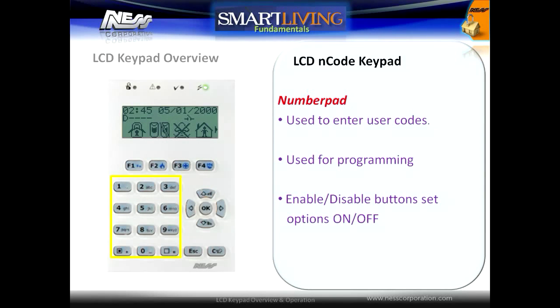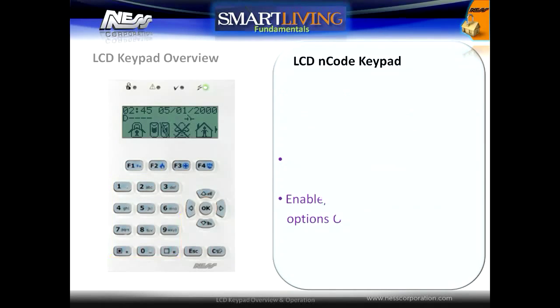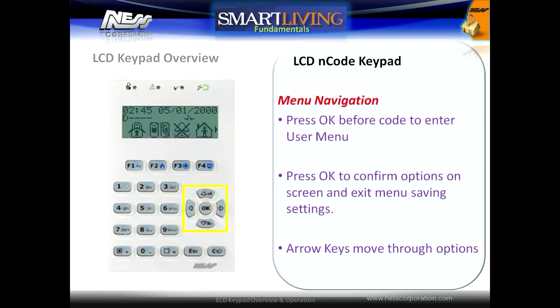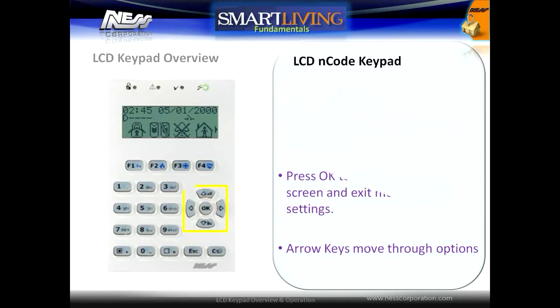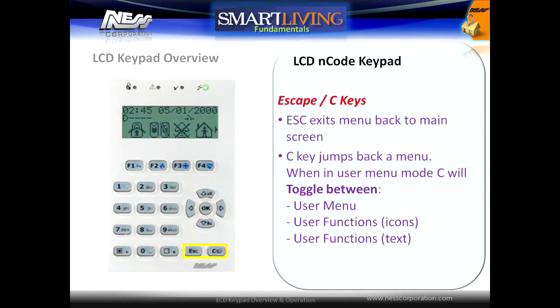The number pad is used for user code entry, for programming, and the enable/disable buttons at the bottom are used to switch options on and off. The menu navigation keys allow the user to navigate through menus. The user menu is accessed by pressing OK before entering a code. The OK button is also used to save any changed settings that a user has made in a menu. The escape key is used to exit the main menu back to the main screen, and will cancel any changes that have been made without pressing OK first.